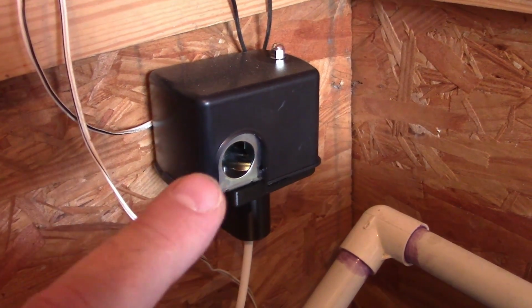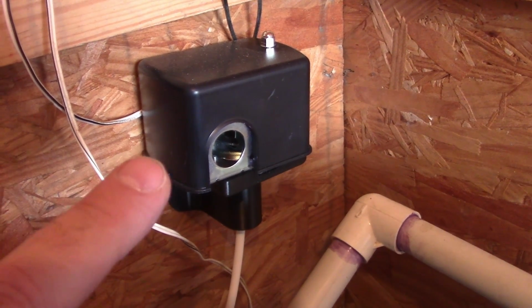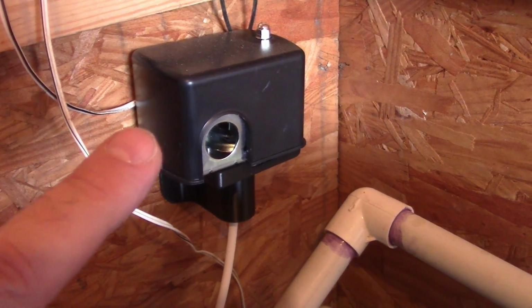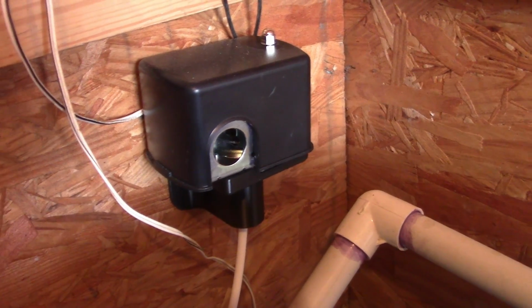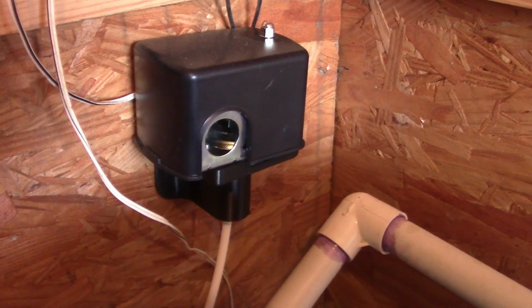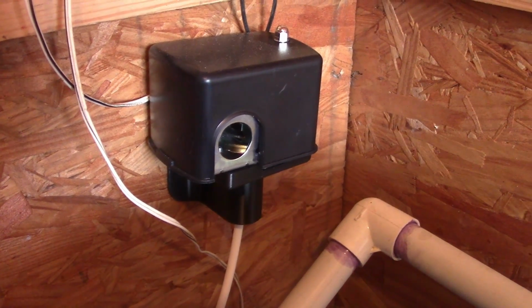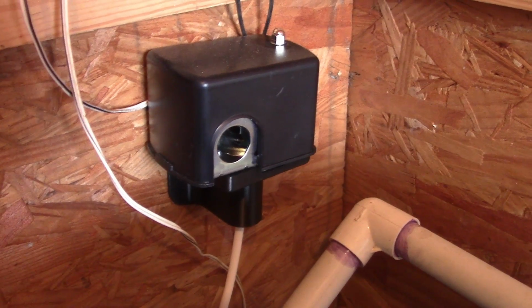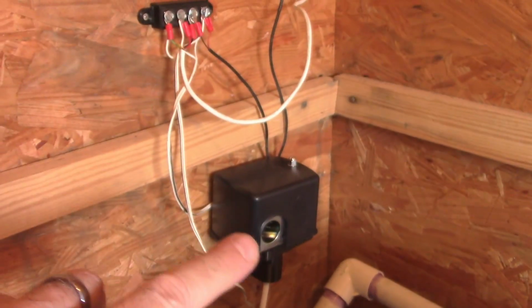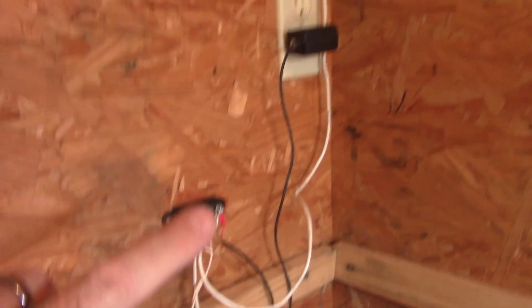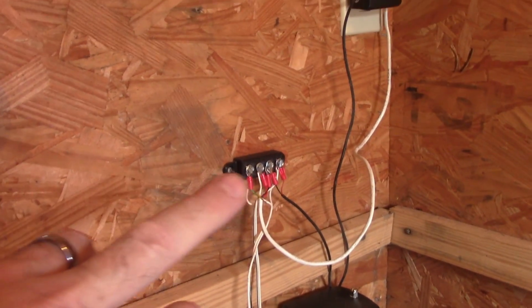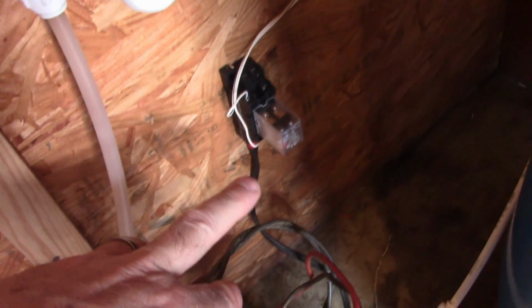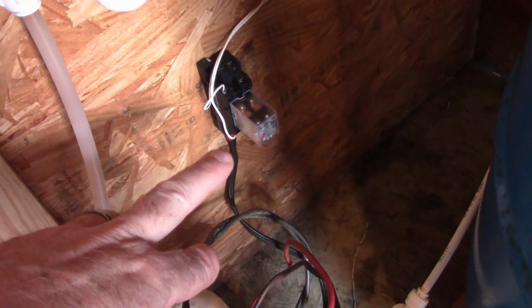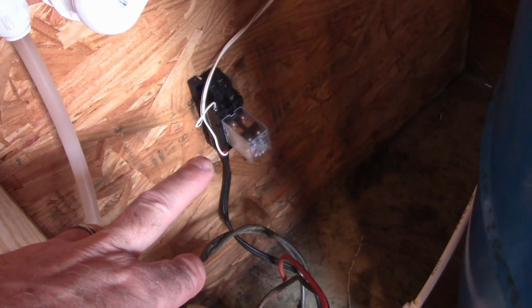And this will trip, just like it's going to turn on the pump, but rather than have it turn on the pump, it's just going to turn on an indicator lamp, and that indicator lamp is on the outside of the building so I can see it from the house. So when the green one comes on, I know the pump's running. When the red one comes on, I know I got a problem and I need to come figure out what's going on. All of this system right here is just 5 volts DC, so there's really not much of a danger to it. I do have a cover that goes over this, and then this down here always has this cover on it. The line coming over here will actually carry 220 volts when the pump is running, so that one is very dangerous, high enough voltage to kill you.